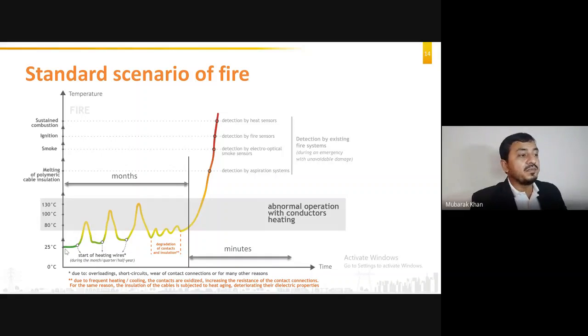Now, what will happen is under the conditions of overload, initially the temperature of the joint will be around room temperature, around 25 degrees Celsius. When the overload comes, the temperature of the joint will increase. It will not become very high, but it will increase up to maybe 80, 90 degrees. When the fault clears, the joint temperature will come down. Again, after some period, maybe a month, a week, or whatever, when the load increases again, the temperature of the joint will increase again. This time to a higher value. And then after the load is cleared, it will come down again.